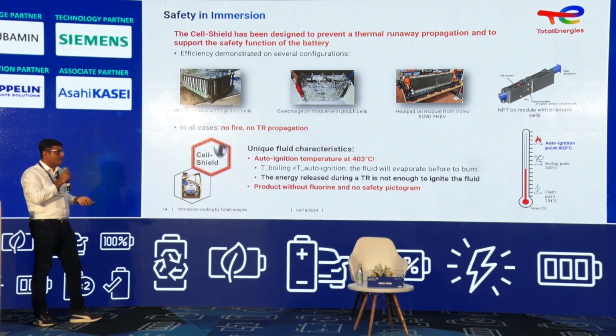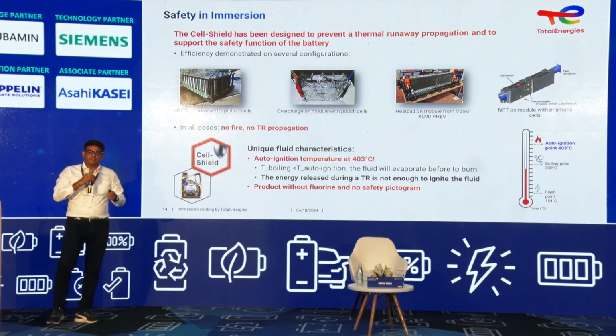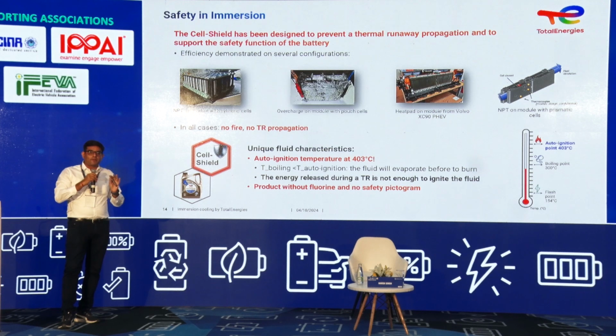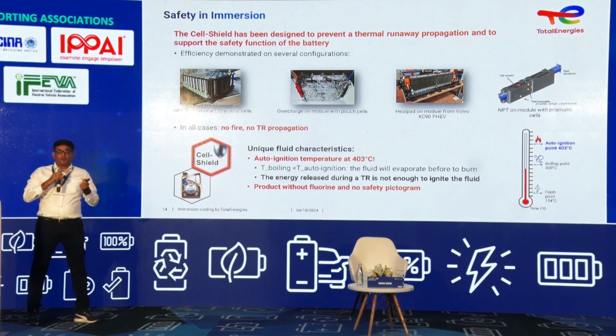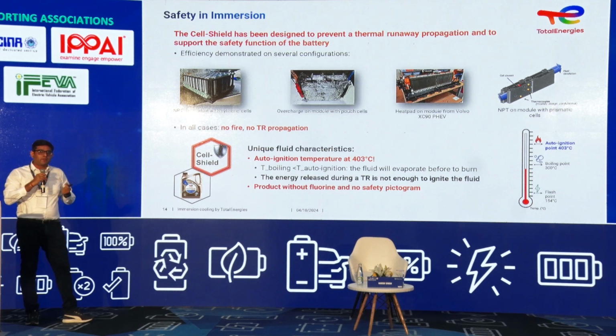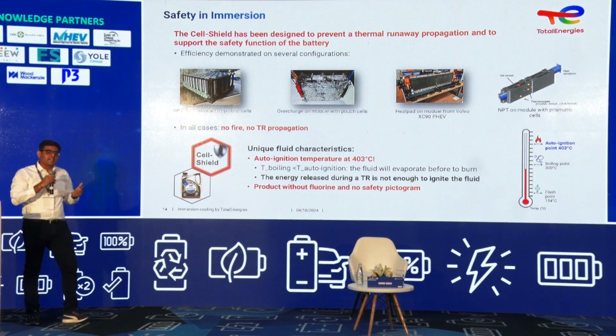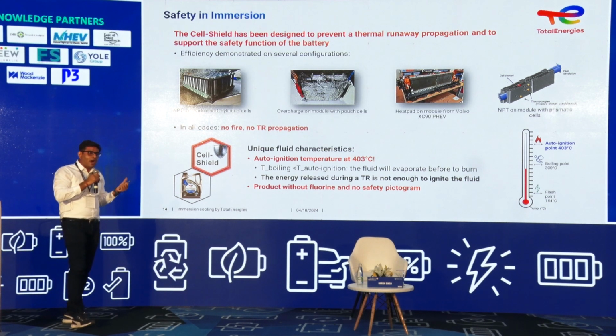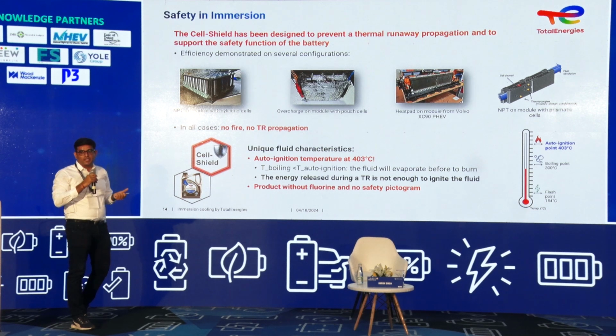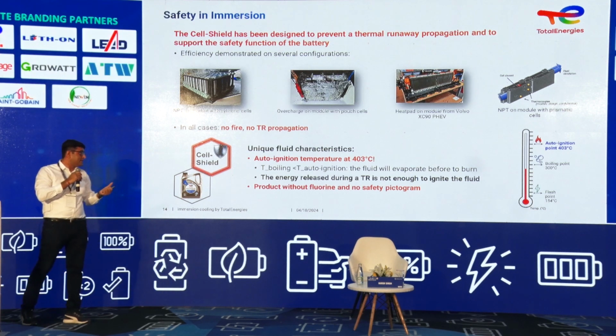Safety is also an important part of this. Thermal propagation should not happen, so the fluid needs certain properties to prevent it. The first property is the auto-ignition temperature, and our fluid has a very high auto-ignition temperature of around 403 degrees Celsius.